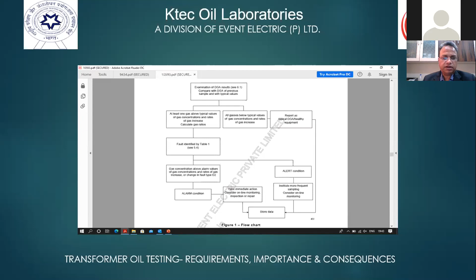So particle count. Basically, in simple words, these are the minute particles which are normally observed in transformer oils. There could be probable reasons from where they come. Particles in insulating oil in electrical equipment may have numerous possible sources. The equipment itself may contain particles from manufacturing. For example, if there is a newly fabricated tank and you have not done proper cleaning inside the transformer, then you can have metal particles in a very small amount. This could be the probable reason.